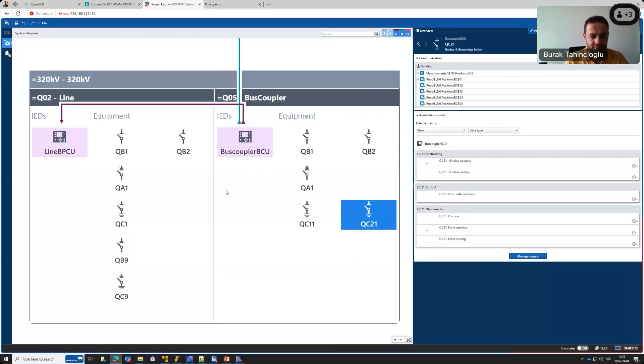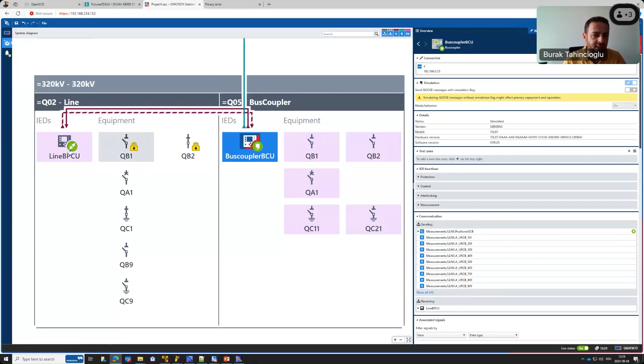Okay, then I would like to simulate this IED without the simulation flag. And I need to go online with this system. So I will look for the IP addresses and find a suitable IP address in this range of StationScout. So I would use my lucky number to connect to these IEDs. I'm saying IEDs because it's one that I simulate and this one. So if this GOOSE is in the network, I can see it's in the network, and this IED is reachable.